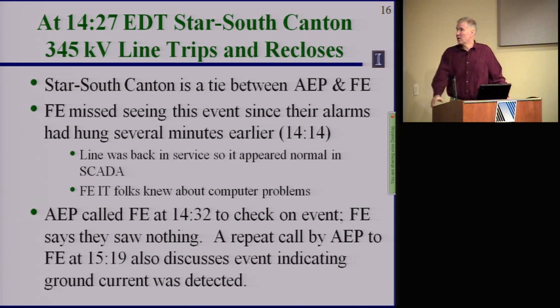What started to get unusual is an hour later, the tie line between First Energy and AEP, it's a 345 kV Star South Canton line, it tripped at 1427. Okay, it tripped and it reclosed, which means that it had a fault on a tree, was later determined, and evidently the tree got out of the way enough, trees can get out of ways, and it reclosed and it was fine. So the line went back in service, and they did not see that on their SCADA. The reason why they did not see it on their SCADA is it was back in service. Normally a trip and reclose would generate an alarm, but unbeknownst to them, about 13 minutes prior, their alarms had hung. Okay, so in the control room, their alarms had hung.